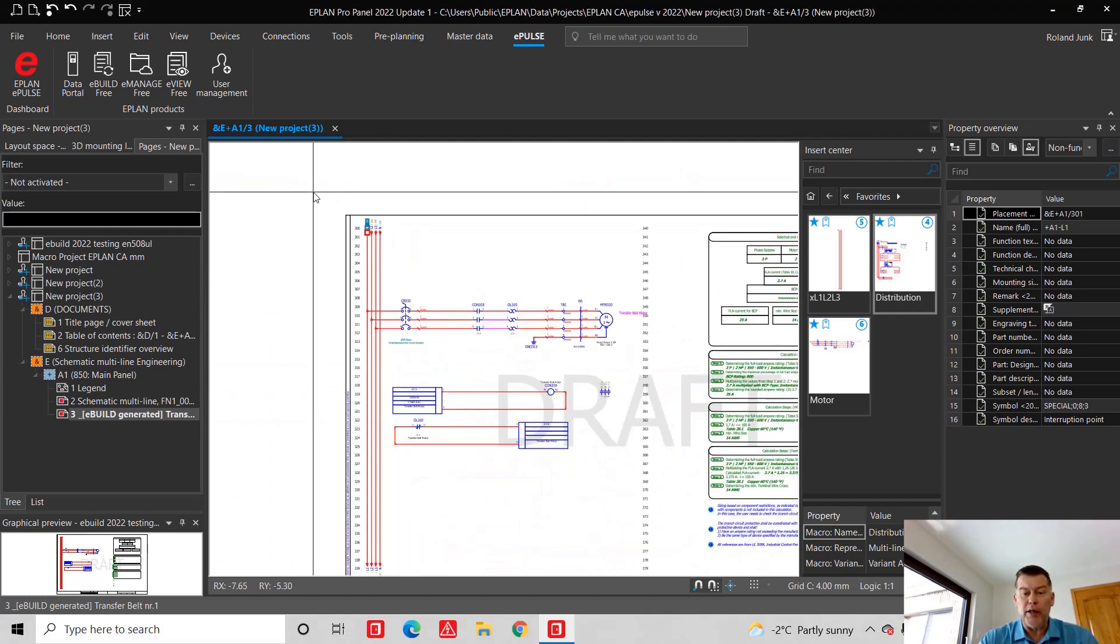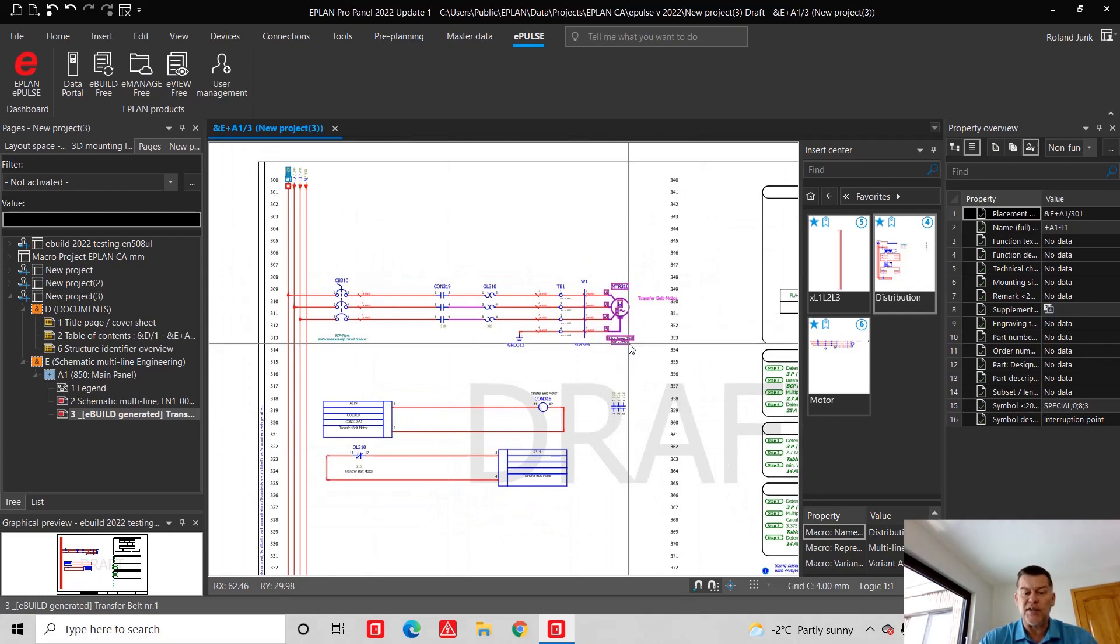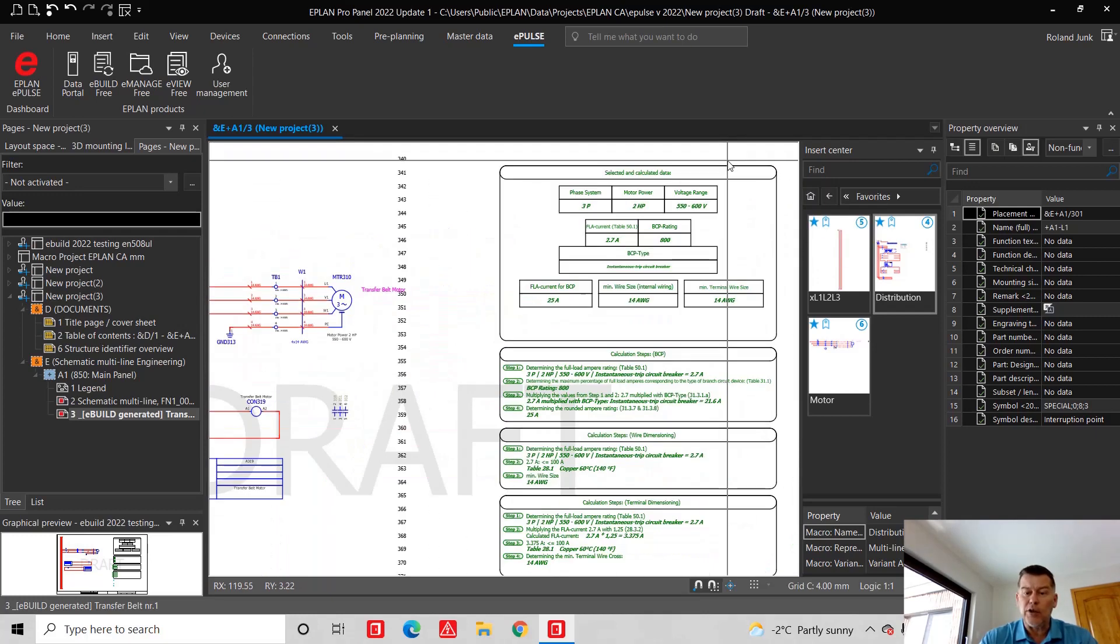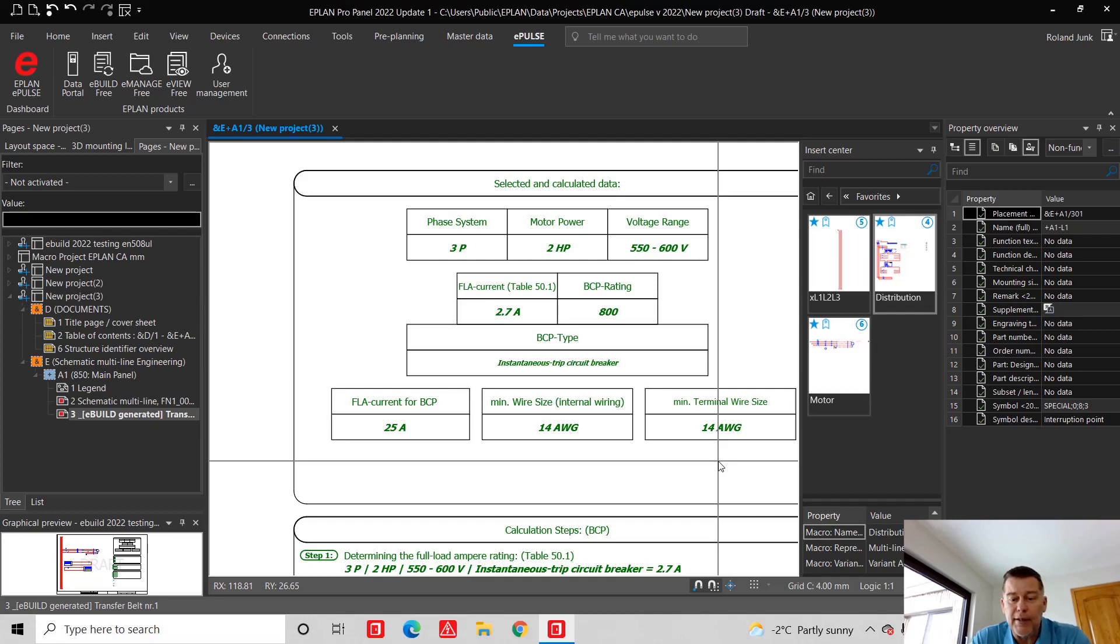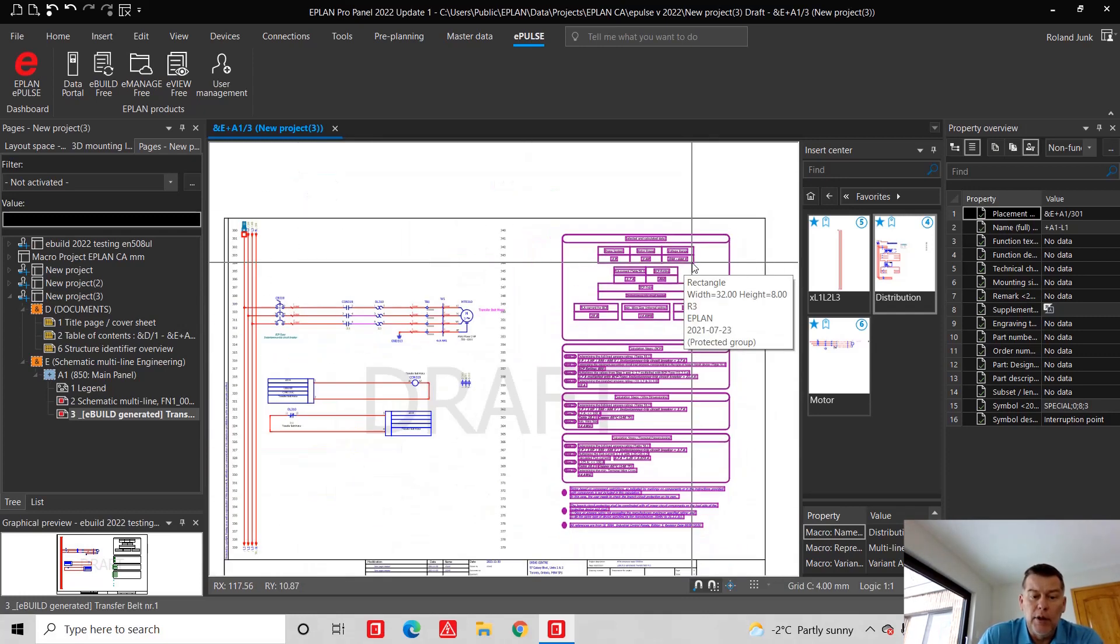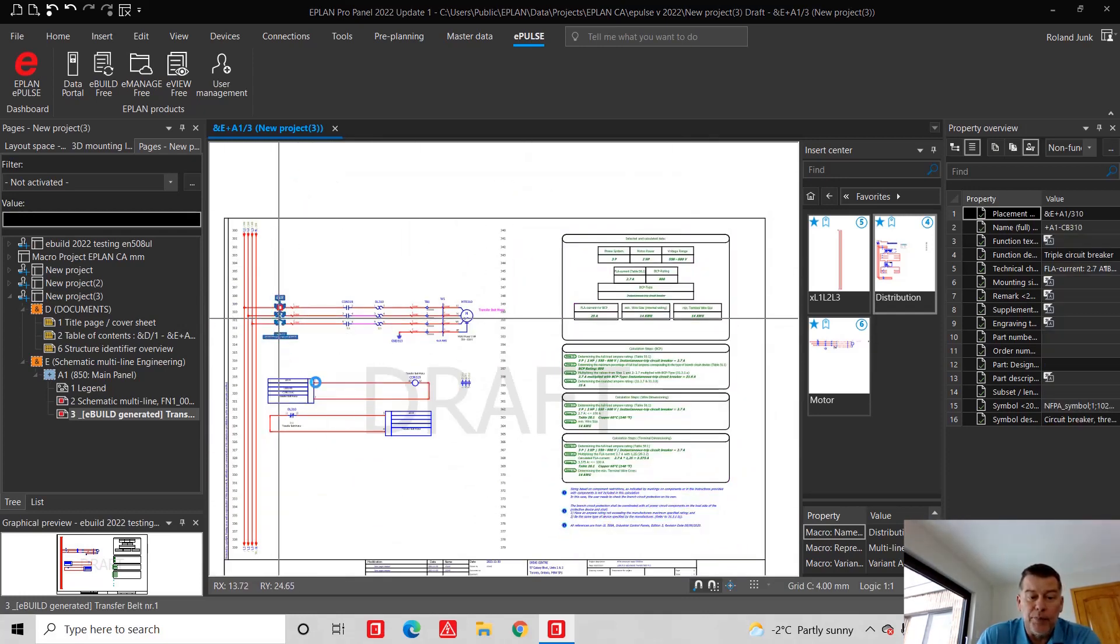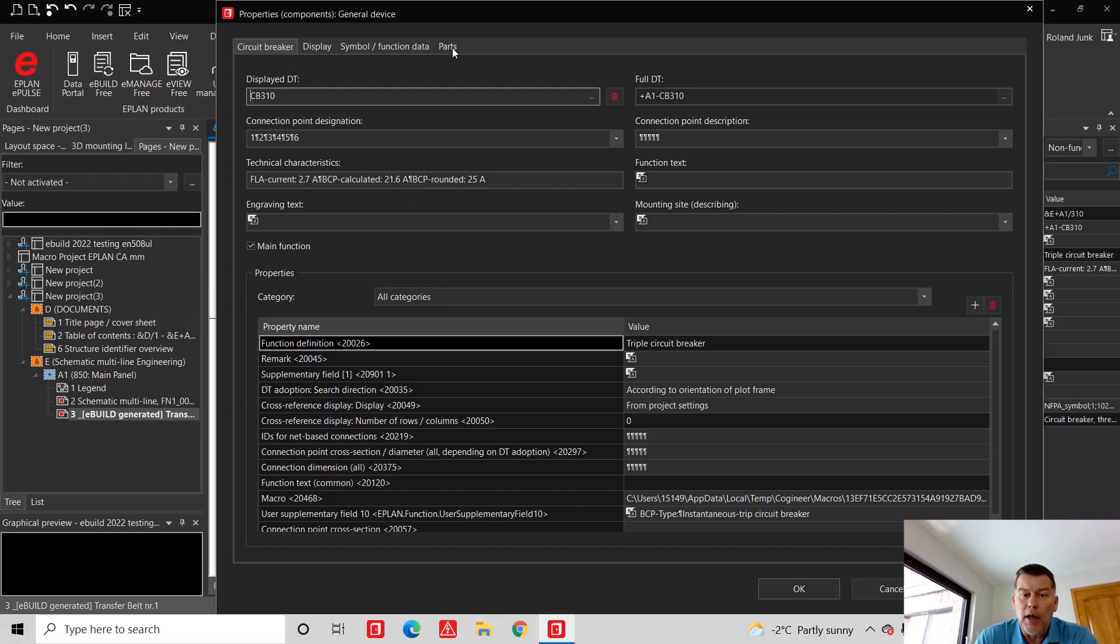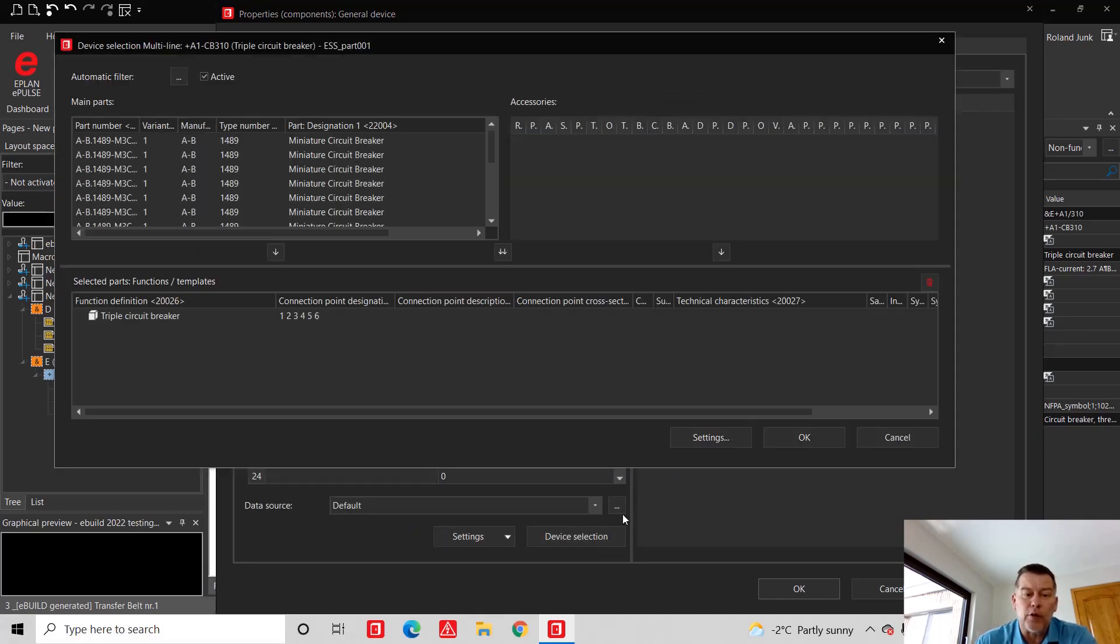What it also did is it actually created this complete set of schematics, plus it also created for me the whole calculation here on the right-hand side. So if I'm looking at these calculations here, it's actually telling me that I need a 14 gauge, which was assigned, and a 25 amp protection for this guy up here. Technically this information all got transferred here. You can see 2.7, 25 amp. I just have to now go and check out what kind of 25 amp I have.